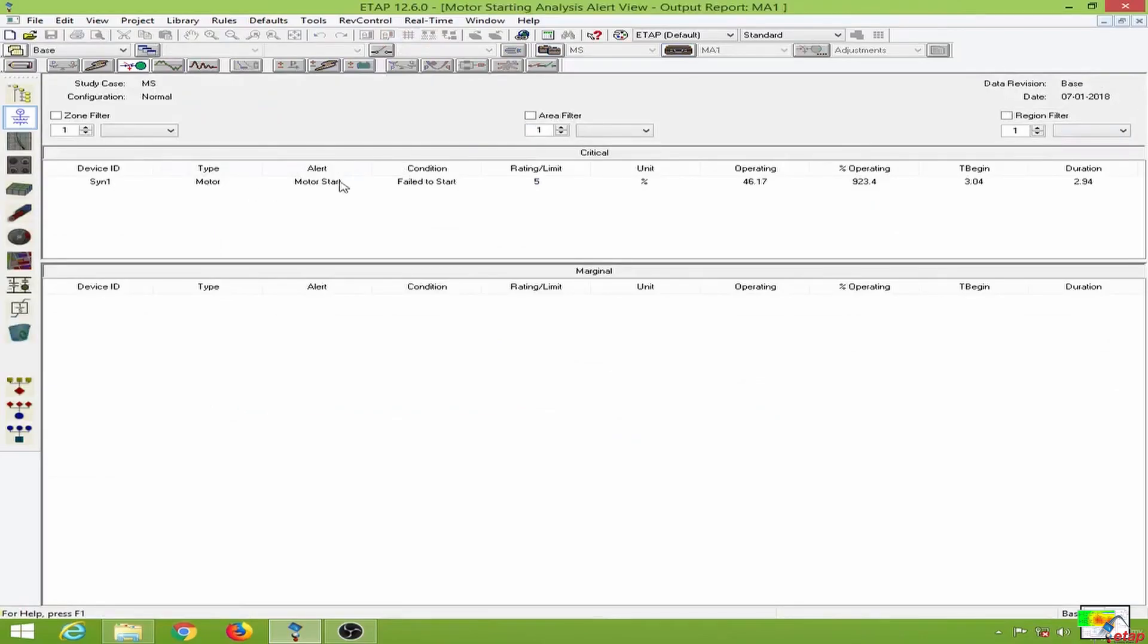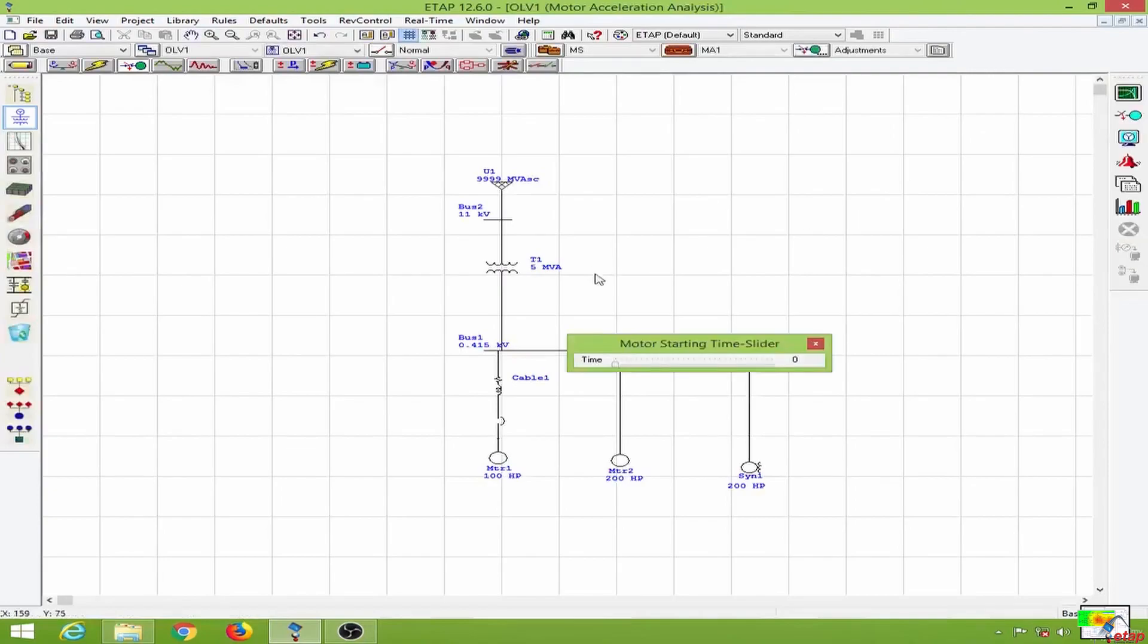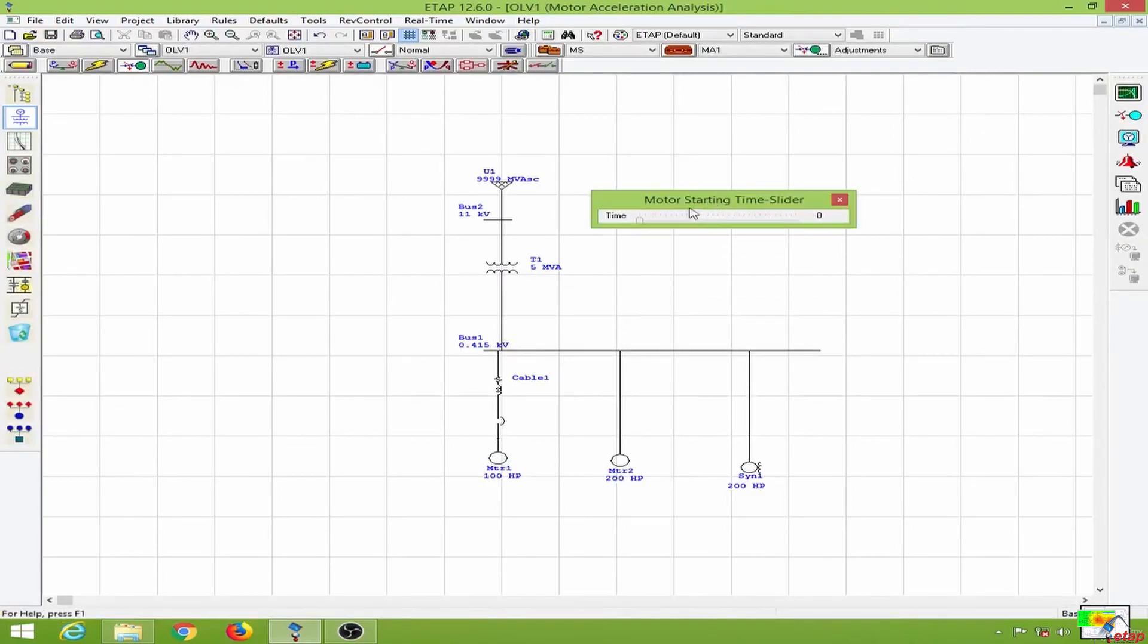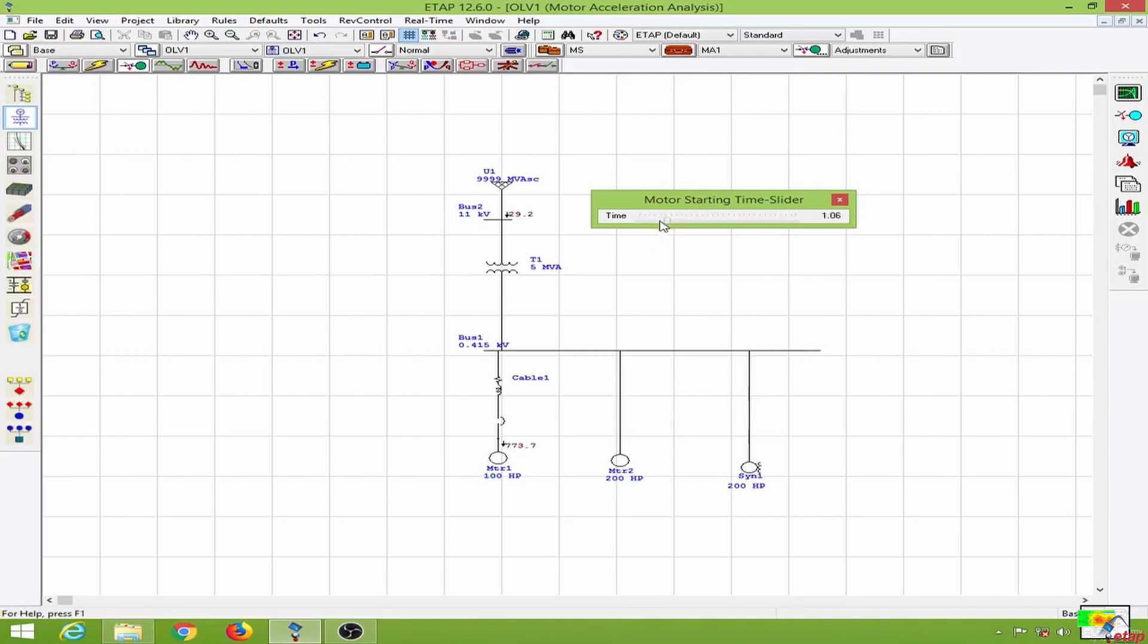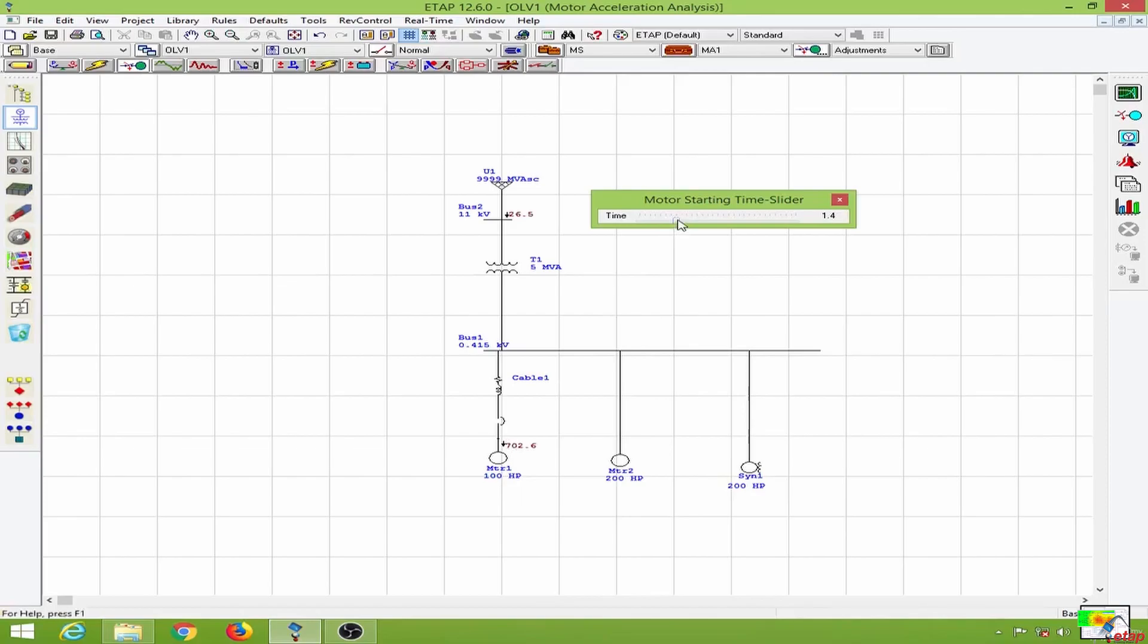I will close this and let us observe the motor starting time slider over here. So at 1 second we have the inrush current for the motor 1, and as you can see this gets reduced with time and the motor starts to pick up speed. You can see this has reduced significantly compared to what it was at 1 second.